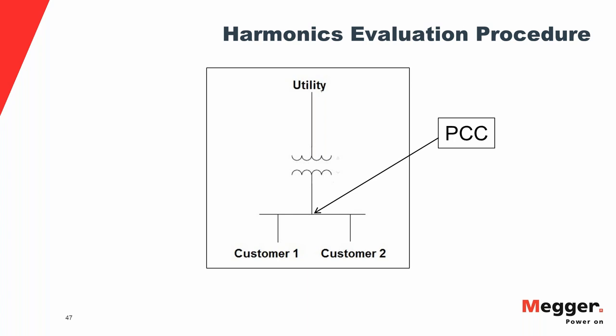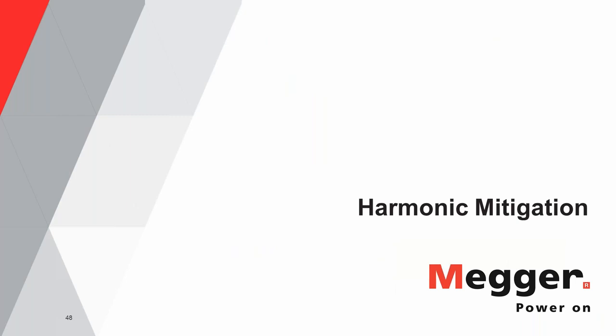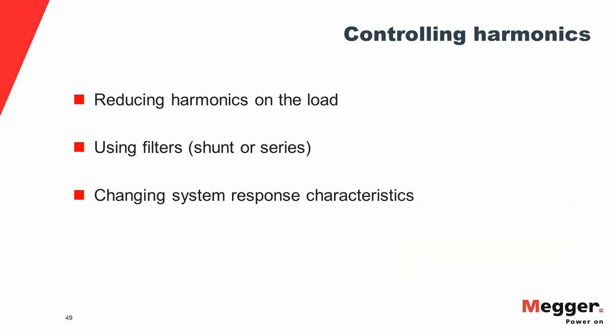Harmonic mitigation approaches include: reducing harmonics at the load itself (e.g., reducing the excitation level of an overexcited transformer); using shunt or series filters — shunt filters bypass harmonics while series filters suppress them; and changing system response characteristics, such as adjusting L and C values to avoid resonance at a particular harmonic frequency.